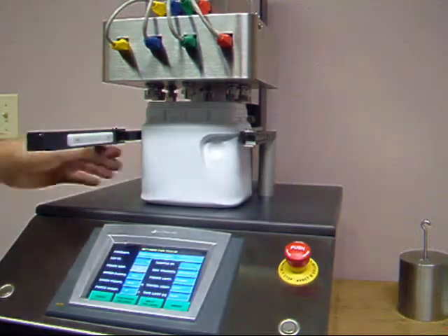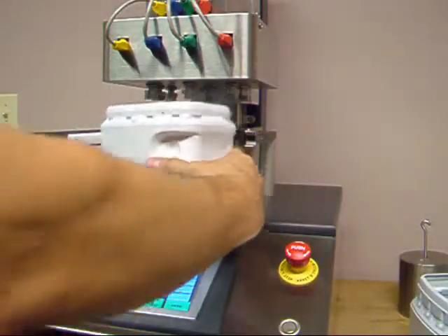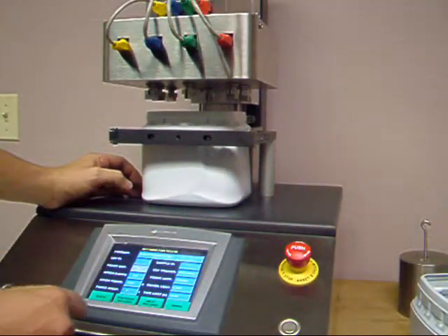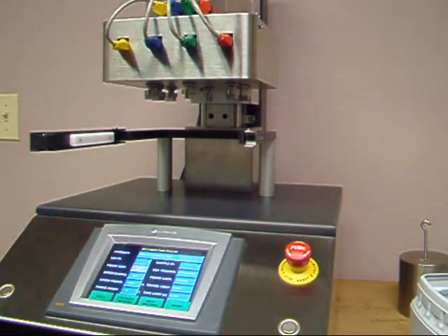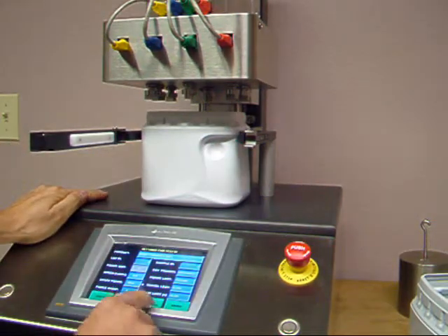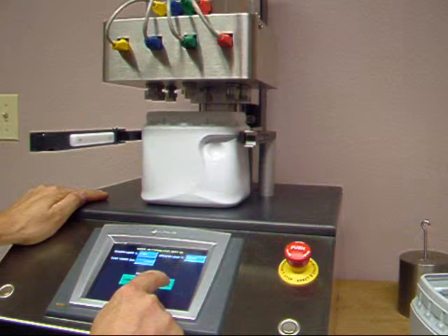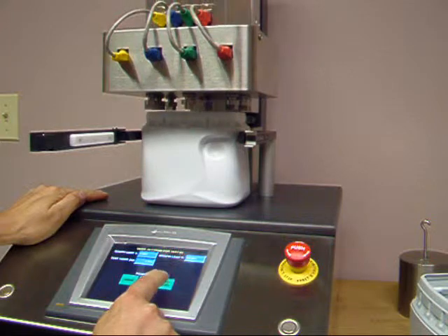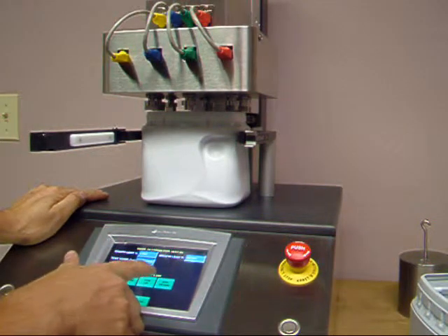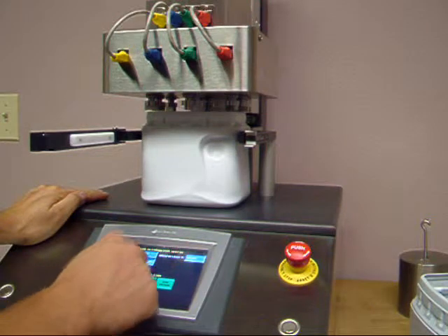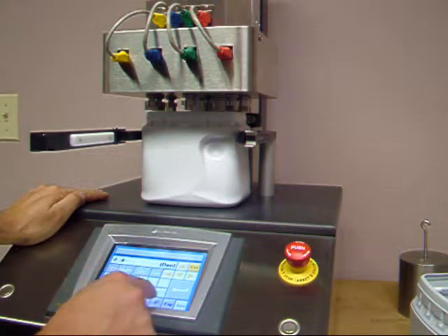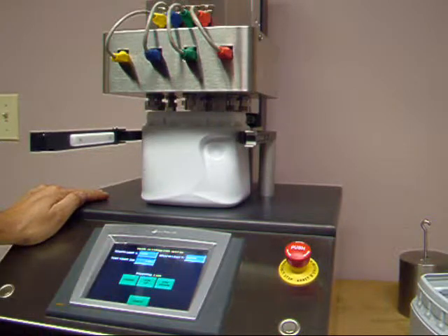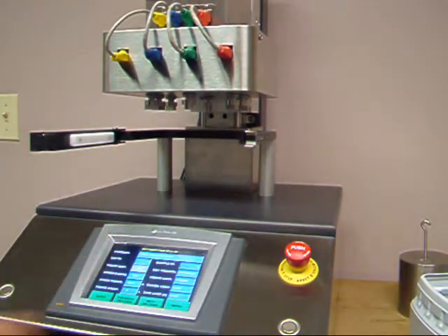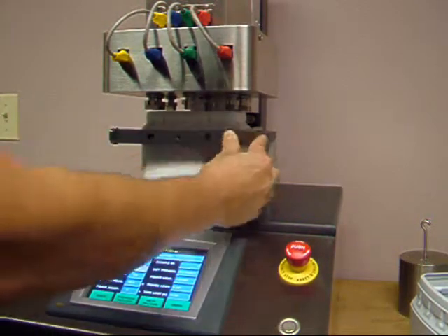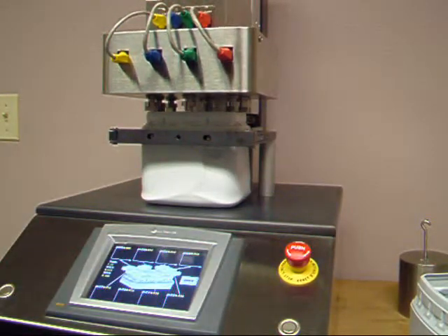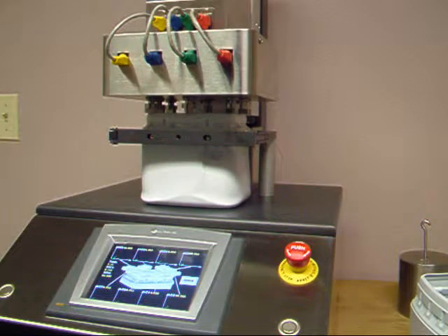So from here you can take the product out, you can put the short bottle in, because I already actually let me show you how you determine the home position for the short one. So you pick the next record, you press more, you use the jog button to drive the carriage down, and then you look at the variable position read 3.4 inches. So you enter 3.4 inches in the test home field, and then you can press the home key, and from this point on this position is set up as the home.